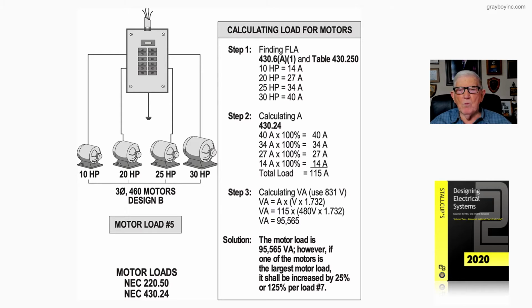Now, in step 1, we start the procedure for calculating the load for the motors. First of all, before you ever deal with motor loads and calculations, go to 430.6A1. And it will refer you for 3-phase motors over to Table 430.250.